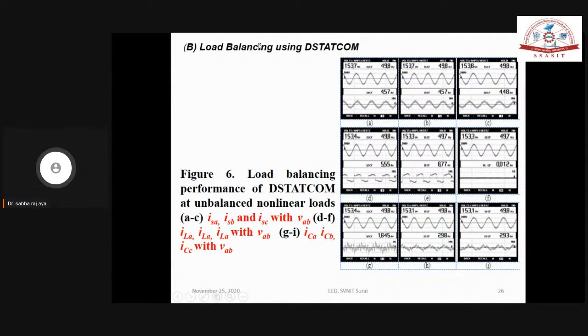What do you mean by load unbalancing? You can see our load is unbalanced. See here, phase A, phase B, phase C. But in phase C, we don't have any load. After some time, if more unbalancing is there, the system is going to be damaged. Some part of it may also burn. But due to this circuit, you are able to maintain all three phase supply currents near balanced value only.